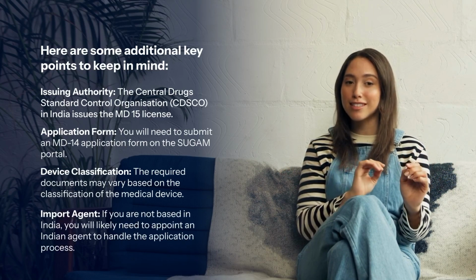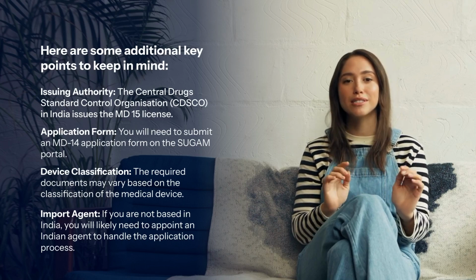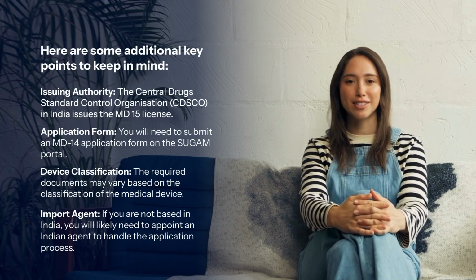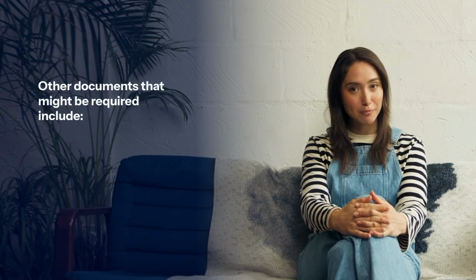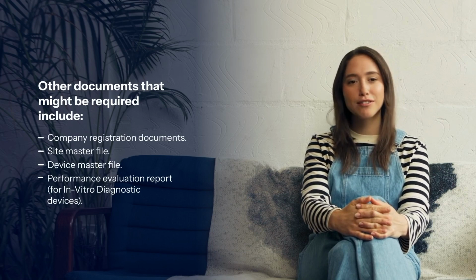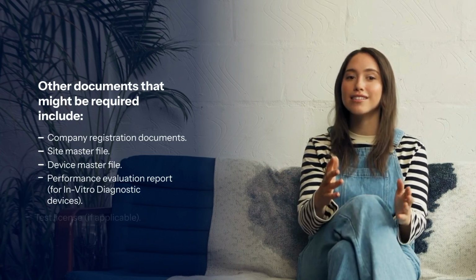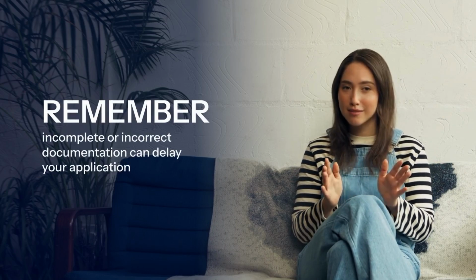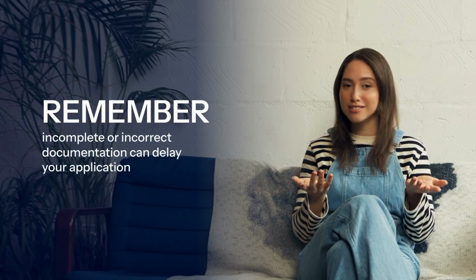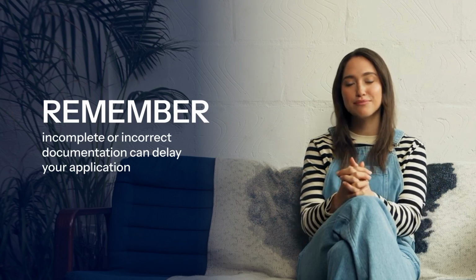Import agent. If you're not based in India, you will likely need to appoint an Indian agent to handle the application process. Other documents that might be required include company registration documents, site master file, device master file, performance evaluation report for in vitro diagnostic devices, test license if applicable. Remember, incomplete or incorrect documentation can delay your application, so make sure everything is accurate.